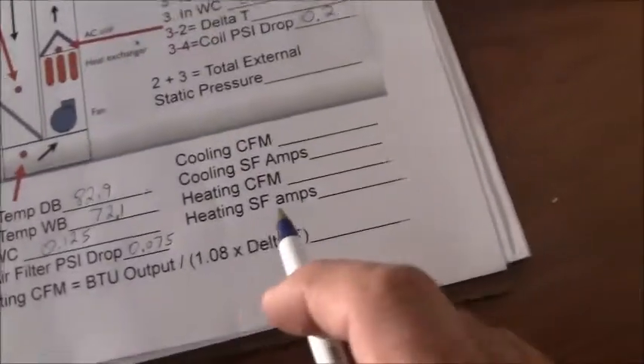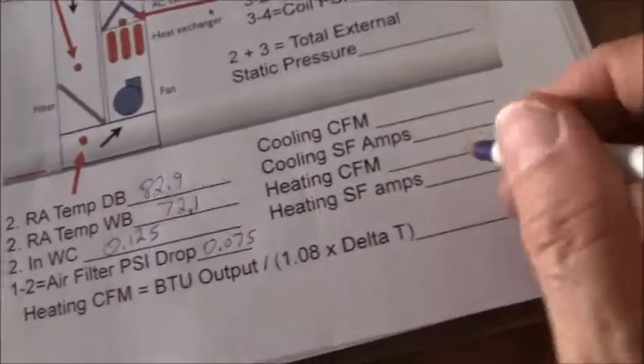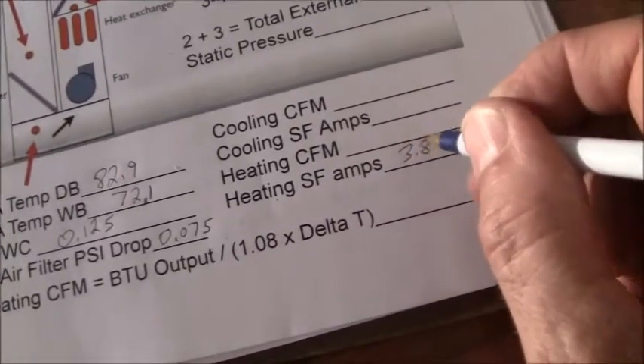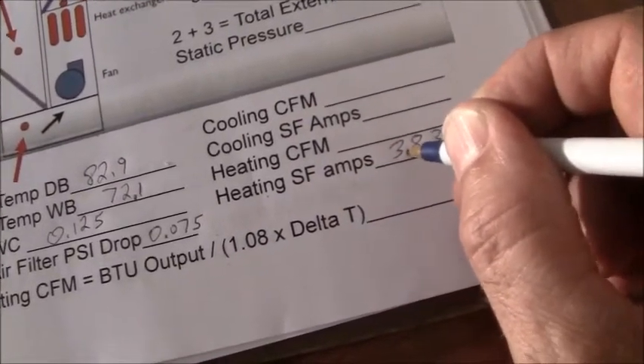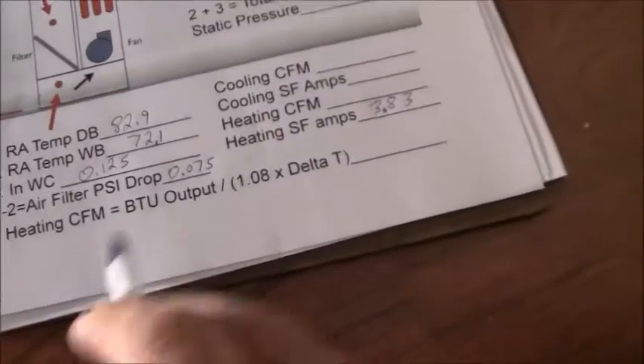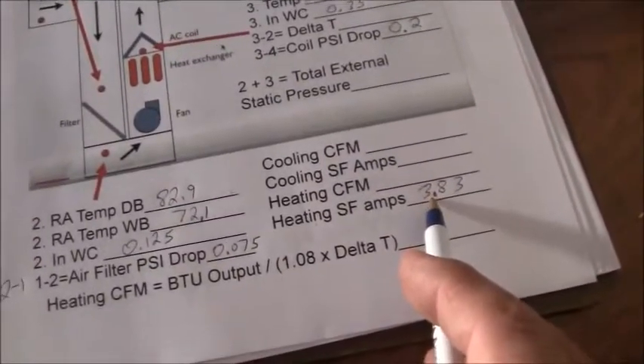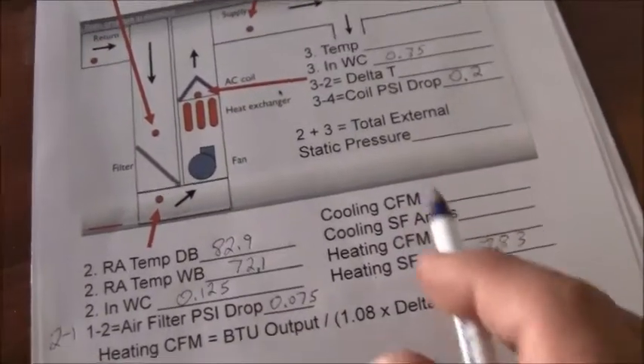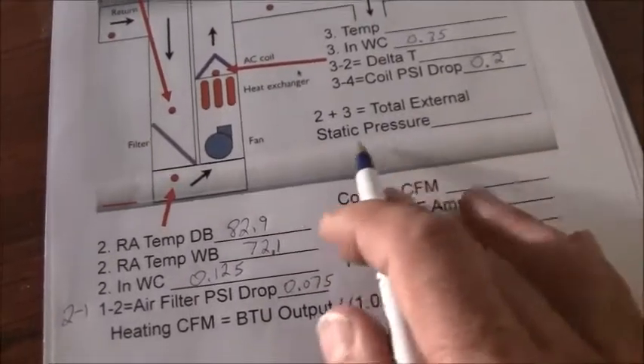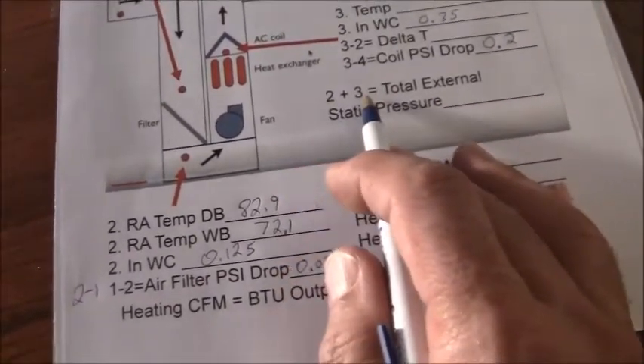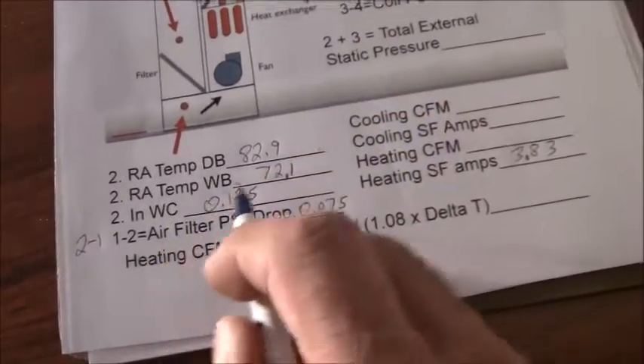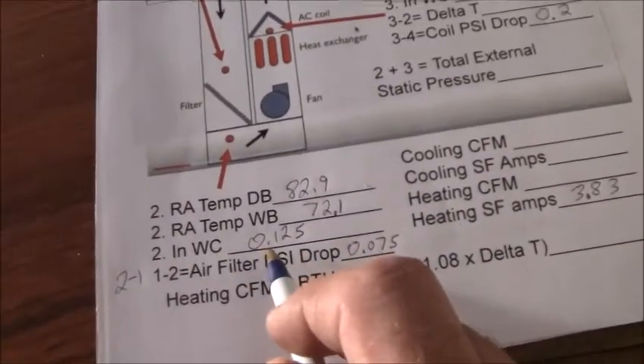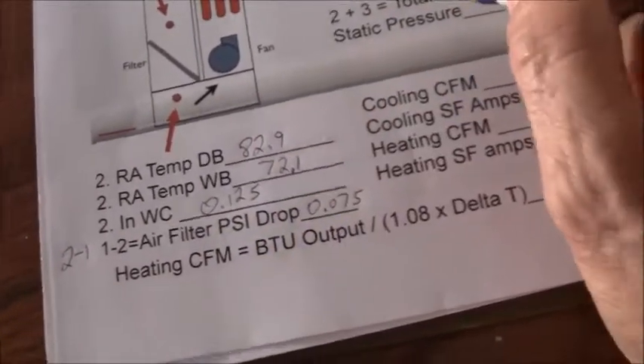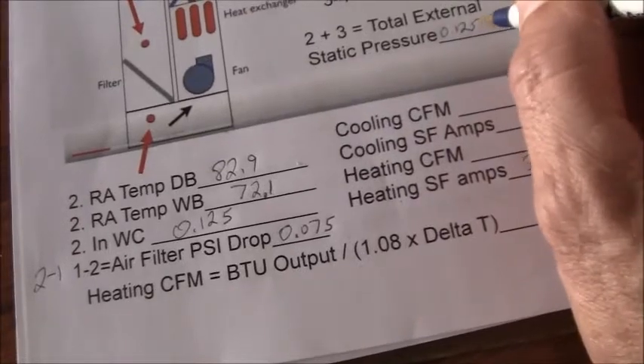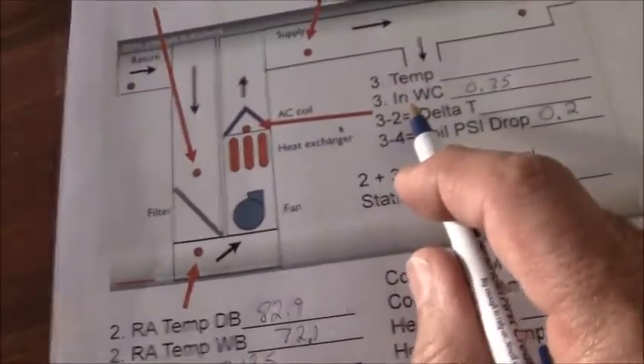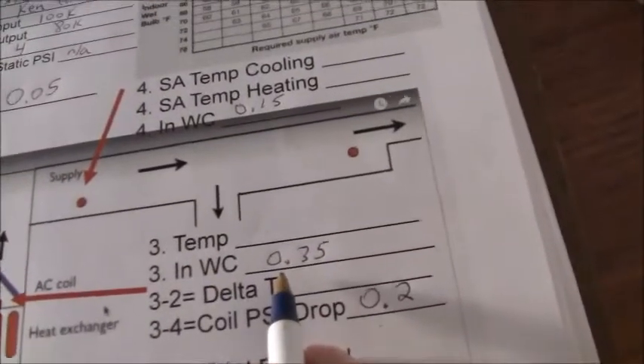And that goes heating supply fan amps 3.83. Okay, now that we know that, we can figure out a few more things. Now we do want to know the total external static pressure. That's going to be 2 plus 3. So 2 is 0.125 plus 3, which is 0.35.